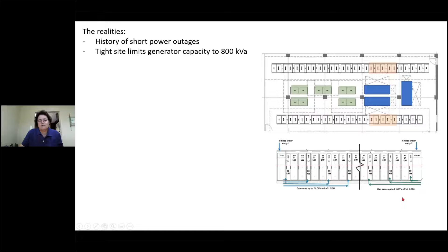We had a 48 rack server farm down in the basement. The campus had a history of short power outages, and we had a super tight site that limited our generator capacity to only 800 kVA, which meant we could only run 10 racks on that emergency generator and the air-cooled chiller supporting it.